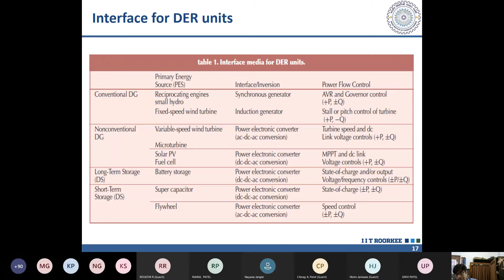In the same way, a flywheel can operate for seconds. It can generate power from seconds to minutes depending on the size of the flywheel. I know one sugar manufacturing company near our campus that was facing a huge challenge with voltage fluctuations, and for this reason they had to run the DGs to maintain the voltage at around 30% load. They implemented a DST project, part of it with the flywheel, and we found that they have considerably saved the cost of diesel.